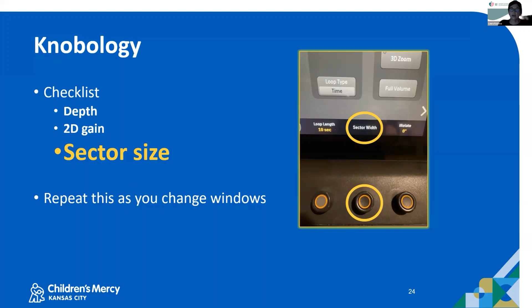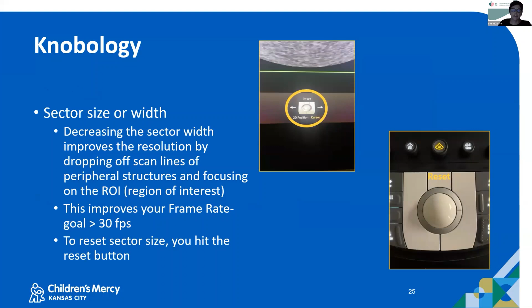Okay, so we adjusted our depth. We've got our 2D gain set. Now we need to talk about our sector size. That's the size of the pie. As you decrease your sector size, you're going to improve the resolution by dropping off scan lines of peripheral structures and focusing on the region of interest. This is going to improve your frame rate. Greater than 30 frames per second is something to shoot for. And then if you decide, I don't like that, I need to figure out how to get back to just my 2D sector, you're just going to hit reset and you'll go back to your default setting.